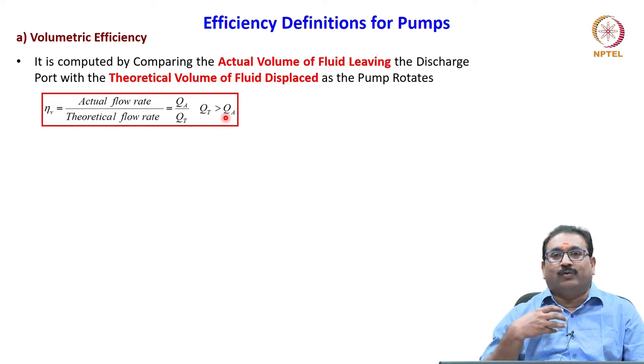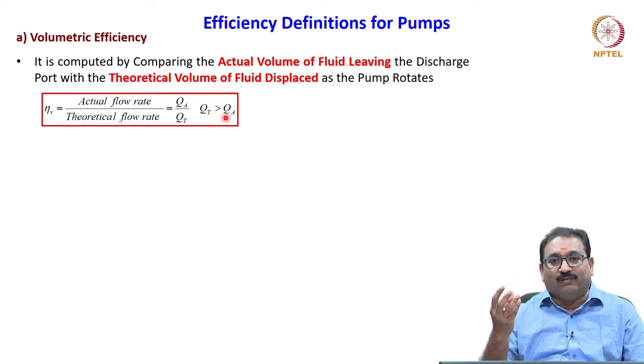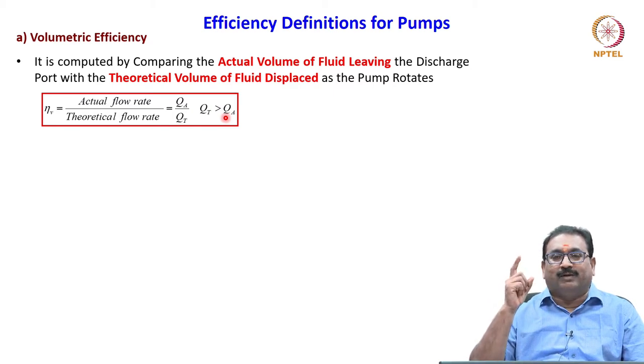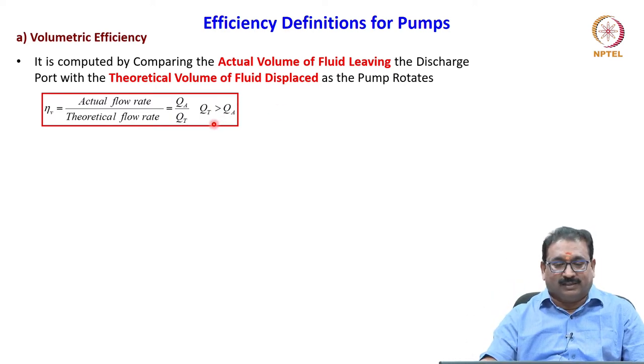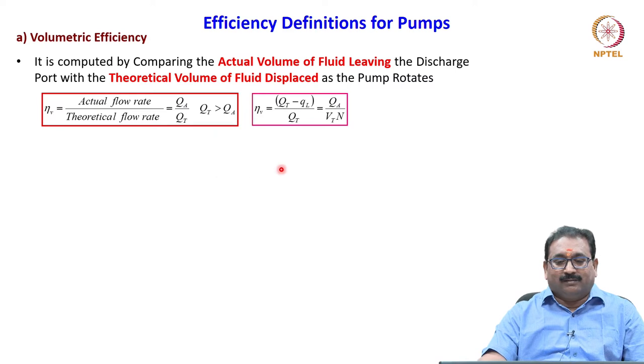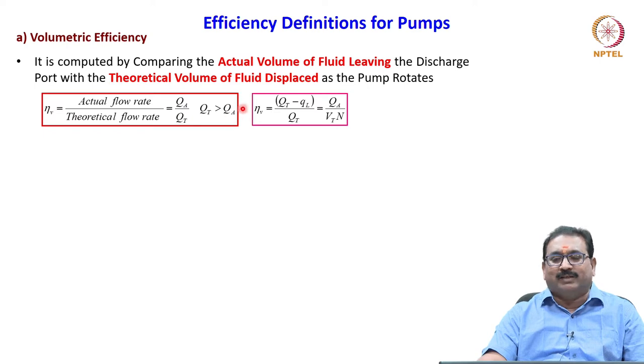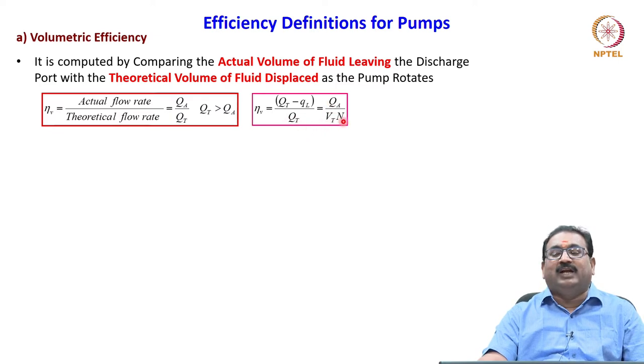We want maximum volumetric efficiency, meaning a close tolerance between the rotating element and the housing. QA is always less than QT — by the leakage QL. So eta_v equals QT minus QL divided by QT, which relates to VT into N.